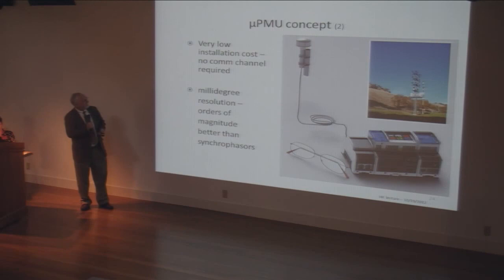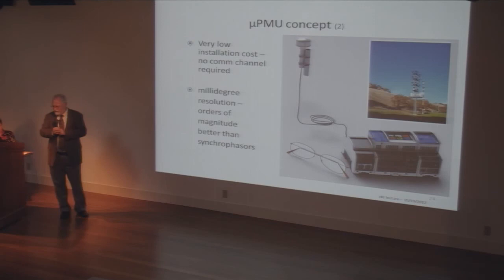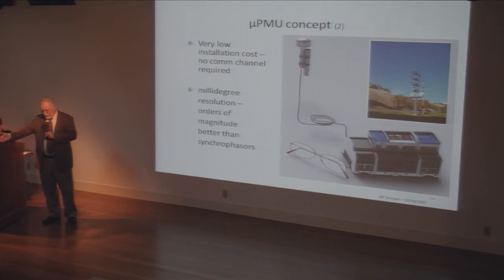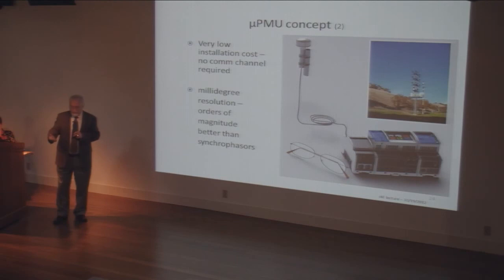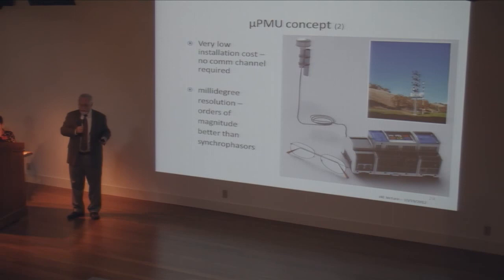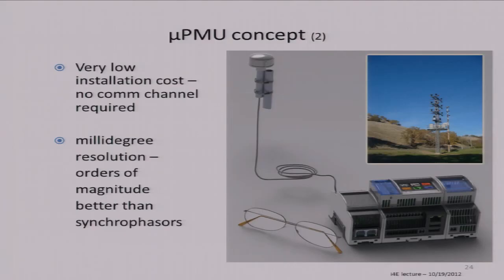A really critical point—a big cost in these phasor measurement unit installations is the communication channel you have to keep open all the time back to the phasor data concentrator, and that's not inexpensive; it has to run constantly and carry a fairly large amount of data. Getting that kind of communication channel on a distribution system would be very difficult. So we've designed this so we don't need a communication channel. We've also done a lot of work, with patents still in progress, to get millidegree resolution instead of a degree or a tenth of a degree—that's what it will take to measure this kind of data on distribution systems.